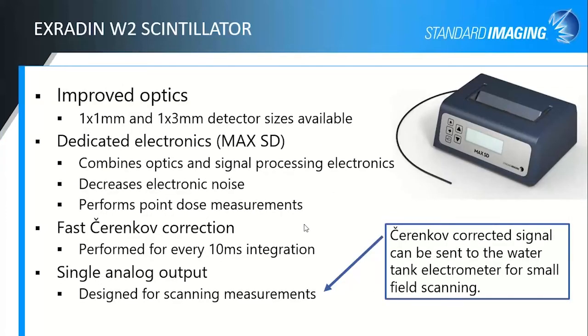With the W2, which is the 2nd generation device, we have improved our detection optics so that we can give you both a 1x1 millimeter detector and a 1x3 so that you can have that small field resolution. You can also have a higher signal device for scanning slightly larger small fields or for comparing with those published W1 measurements. There are dedicated electronics here that do both the optical signal collection and the 2-channel chromatic correction. That was part of what helped us go down to the 1x1 scintillator as well, because we could decrease our electronic noise floor with this integrated system.